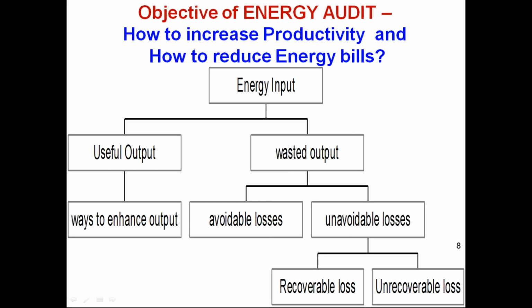In this, you take any process or any equipment in the utility, especially the motor or pump or blower or compressor. By measurements in the energy audit, we see whether we can increase the productivity of the machine or reduce the energy consumption of the machine. Here, for the given energy input, the wasted output has to be corrected. But for any equipment you take, whether a transformer or a pump or a motor, definitely the avoidable losses are more than the unavoidable losses. A motor will definitely have a no load power consumption, but we cannot reduce the no load consumption for a given motor in the industry.